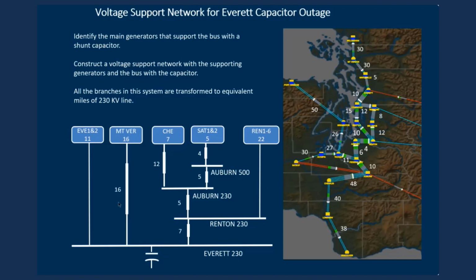So when you see the numbers on this diagram, that means that that line there is equivalent to 16 miles of 230 kV. And this is the main concept. Normally when we think about power systems, we talk about the resistances, the reactances, the capacitances, and we can convert those to a per unit system. But those are very difficult things because they're not integers. They're difficult for an operator to actually use with a rule of thumb or calculate in real time.